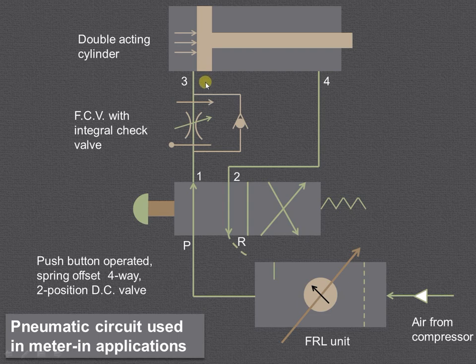As the air entering the cylinder is controlled, it is known as meter-in application. The air from the other side can easily go from port 4 to 2, and from 2 to R, which is the atmosphere.